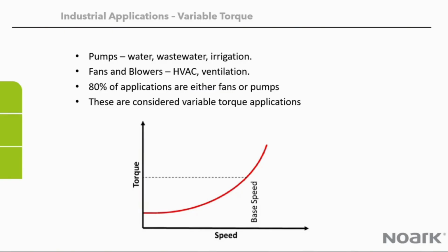VFDs are broken down into two general categories. We have what we call variable torque, and we have constant torque. Variable torque covers about 80% of the applications in the industry: your pumps, your fans, water, wastewater, heating, cooling. These are considered variable torque applications.